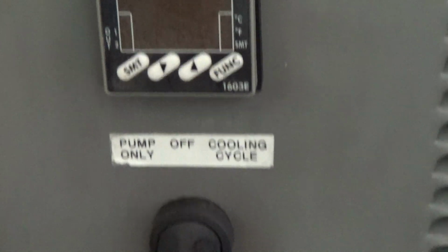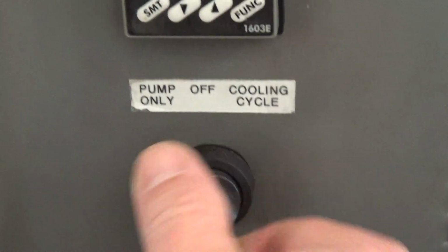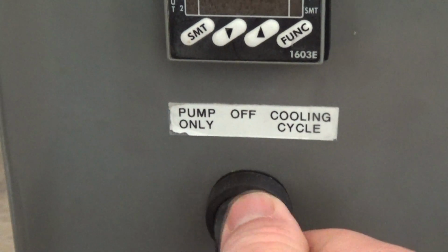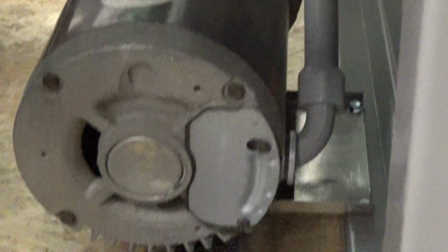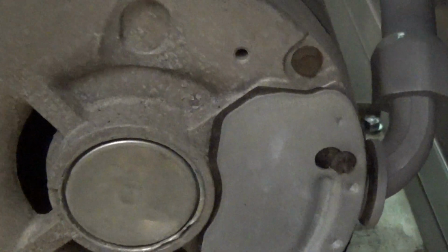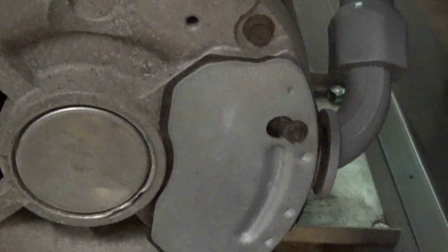It is a 3-phase unit, of course, so when you are doing your initial setup, you should check the phase rotation by looking at the rear of the pump and just toggling it when it's in the off position, by having somebody look at the rear of the pump and toggle the pump briefly. We should be able to see that the pump is rotating clockwise when looking at the rear. And with a flashlight or just looking in, you'll be able to see when you toggle it, the windings or part of the motor rotating there at the rear of the pump.